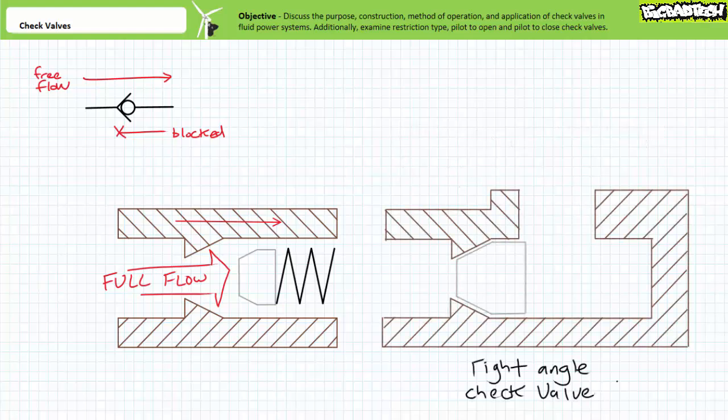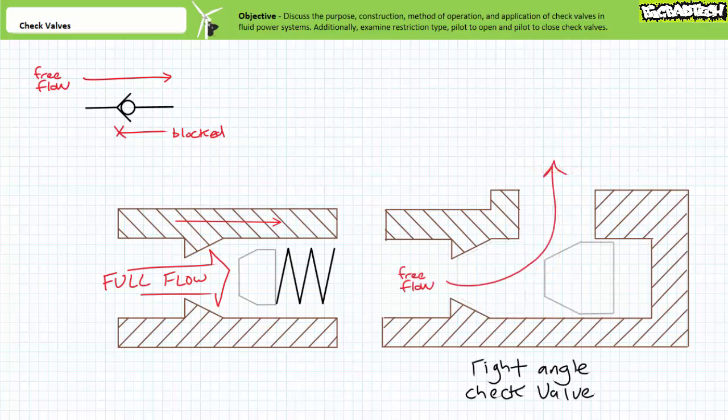For this reason, consider an alternate arrangement of a basic check valve called a right angle check valve. In this case, fluid flow is still blocked from out to in. However, when flow is routed into out, the poppet is forced out of the path. Free flowing fluid still has to make a hard 90 degree turn, but it sure beats zigzagging around an obstruction directly in the path.